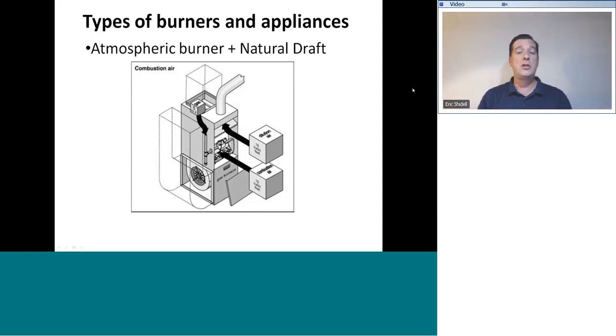And if conditions are not such that that sucking or that pulling action exists, there won't be a good draft. If there isn't a good draft, it's very difficult to get a good mixture of fuel and air, and that is why we said earlier one of the main causes or primary causes of incomplete combustion is a poor draft. There are a lot of factors that contribute to draft, which we will touch on as we move forward.